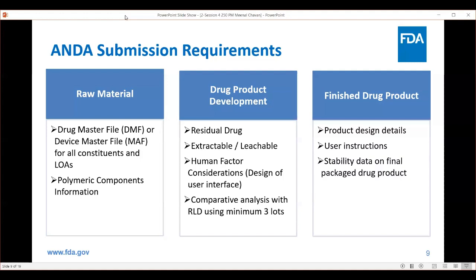During formulation development, the data from these studies such as residual drug, extractables, leachables, or human factor considerations shall be submitted. Additionally, comparative analysis with RLD using a minimum of 3 lots is highly recommended in the ANDA submission. Special considerations for finished drug product are product design details, which shall include how the drug substance is incorporated with the device constituent part. For example, whether it's a matrix release design, whether it's a reservoir type system, or whether there is a drug which is a solid core and contained in a ring. Engineering drawings as well as cross-section schematics are required.